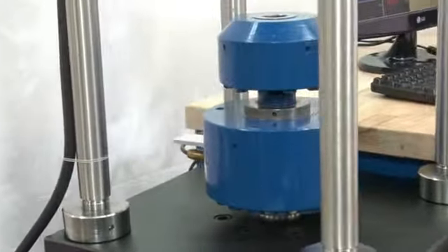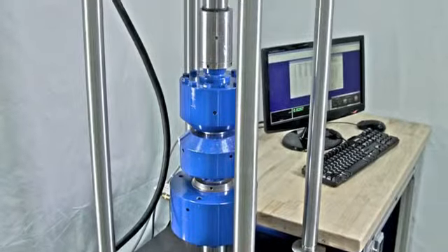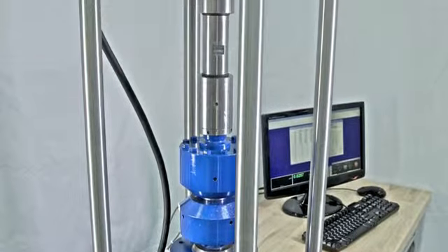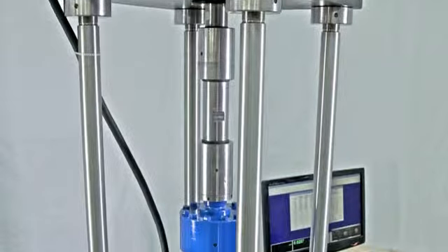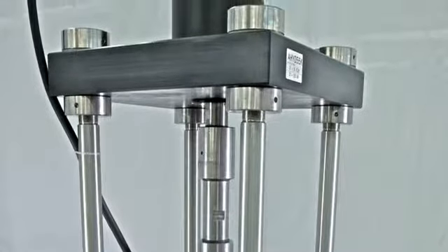Finally, all three load cells are completed in the load string stack. The completed stack now provides the system feedback and control, the reference standard, and the test load cell to be calibrated at the top of the stack.